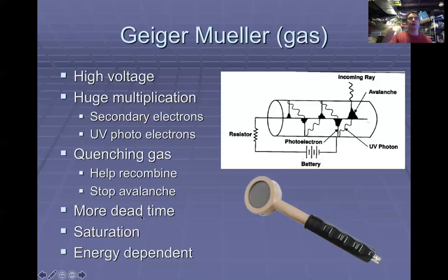And as your count rate gets higher and higher, this dead time becomes more significant. It gets to the point where you might be missing more counts than you're getting. There are ways to correct for it, but ultimately at that point, a GM is probably not the meter you want. If you're in that intense of a radiation field, you're going to want an ion chamber that can better handle the onslaught of ionizing events.